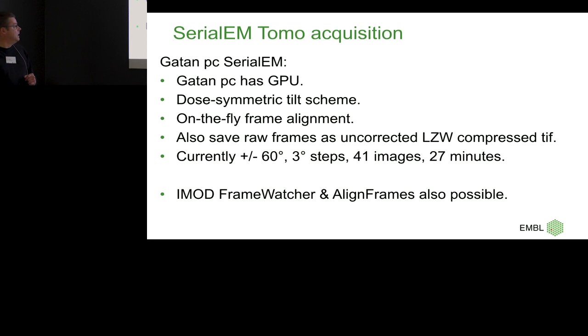Everybody seems to be happy with that. With IMOD FrameWatcher and AlignFrames you can also use this for tomograms — where all the data is just written, you don't do frame alignment, and once the tilt series is finished, it pulls all the data to your support PC with IMOD, does all frame alignments, sorts your stack, and you get a completely frame-aligned raw tilt series out.